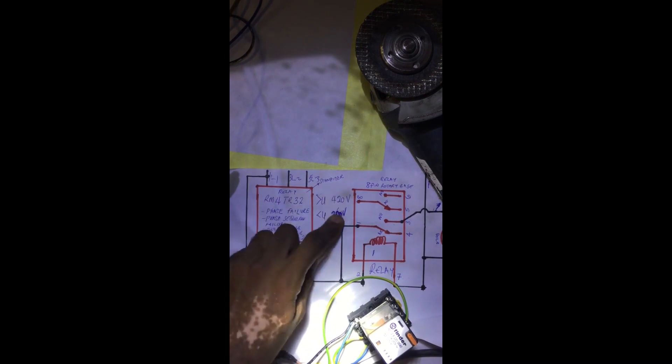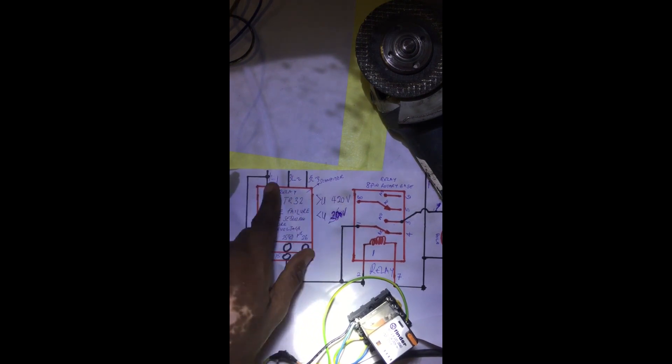You may also decide that your equipment cannot take anything above 400. You can also set this upper threshold as it pleases you. Once these parameters are met and the phase sequence is in order - red, yellow, and blue in order - and the voltages are right, the upper and lower limits are there, this relay will conduct.